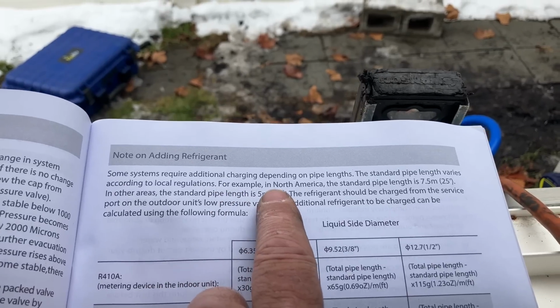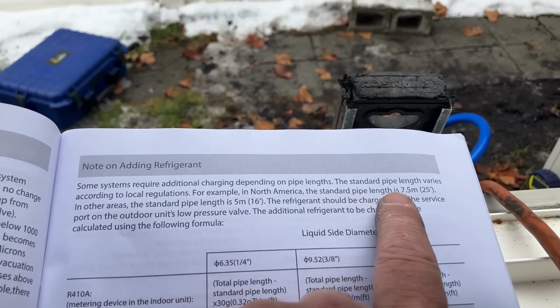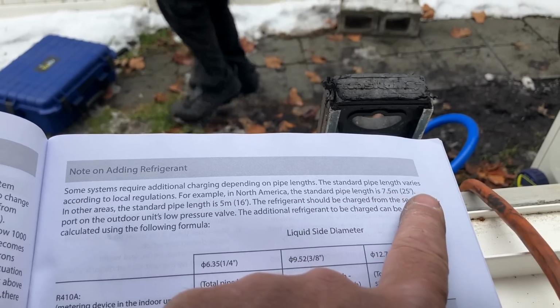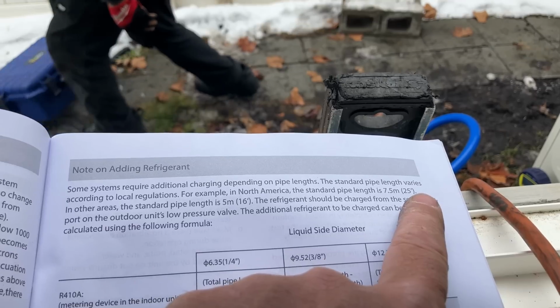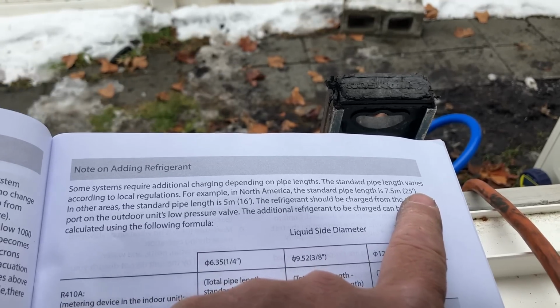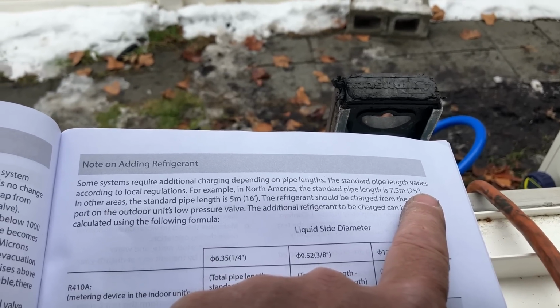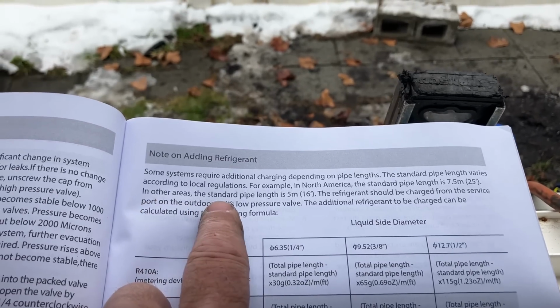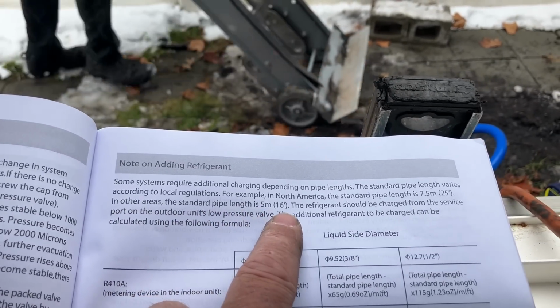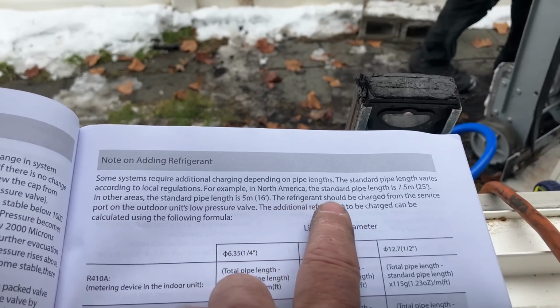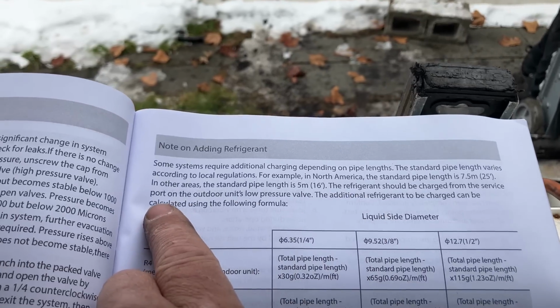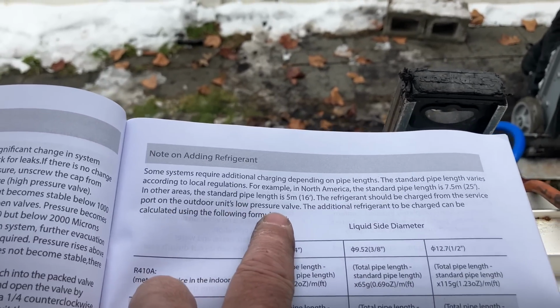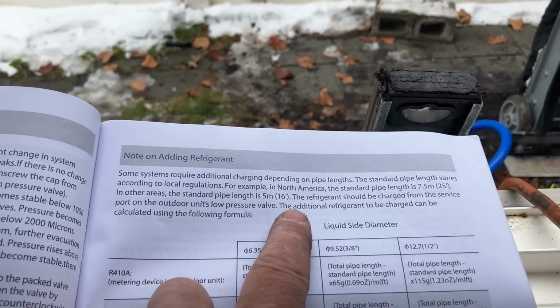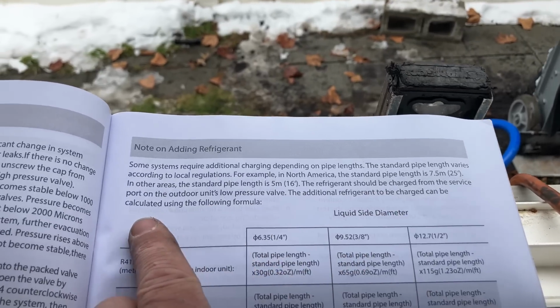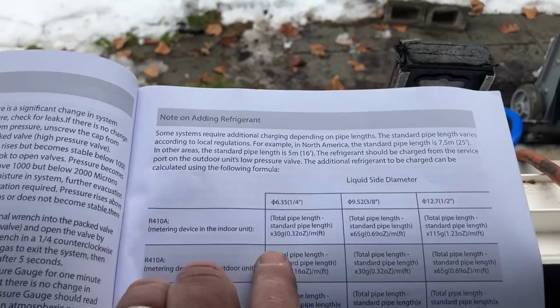For example, in North America, the standard pipe length is 7.5 meters, 25 feet. Okay, if you want to tell me that, I think most line sets are well into 50 feet, if not more. In other areas, the standard pipe length is 5 meters, 16 feet. The refrigerant should be charged from the service port on the outdoor unit's low pressure valve. The additional refrigerant to be charged can be calculated using the following formula.